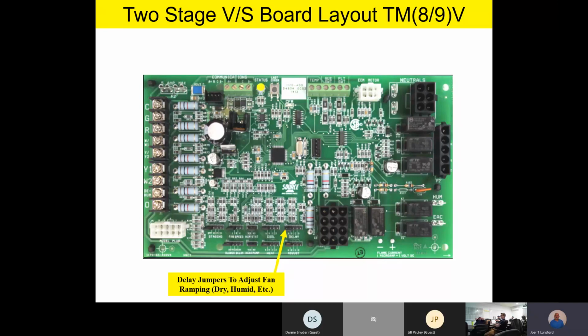If you're out in the high deserts of New Mexico, and you don't have any humidity out there, but you want your fan coming on right away, it'll ramp the fan straight up, over 10 or 15 seconds, to 100% airflow. And then when the call for cool goes away, it just ramps the fan down quickly, maybe 30 seconds, and so on.